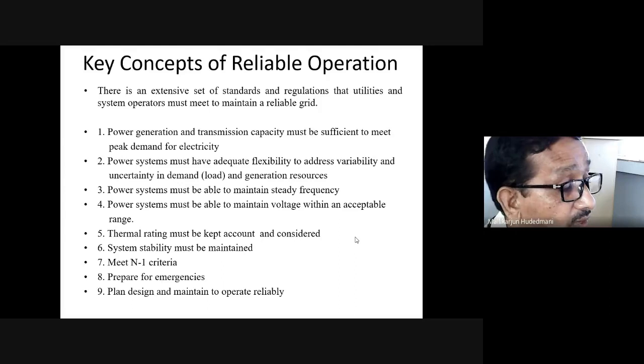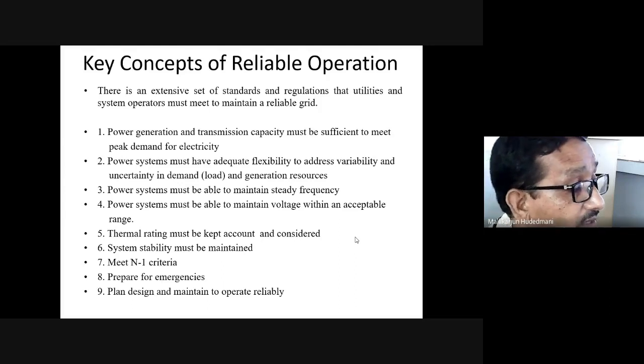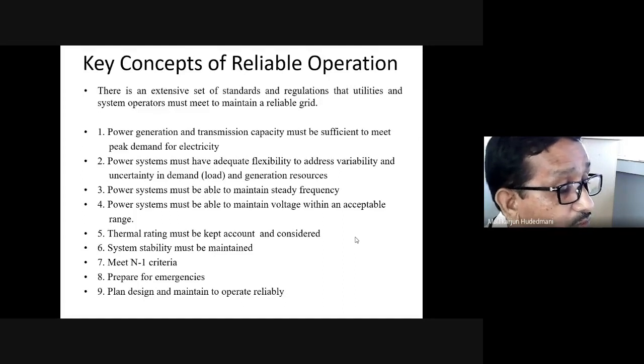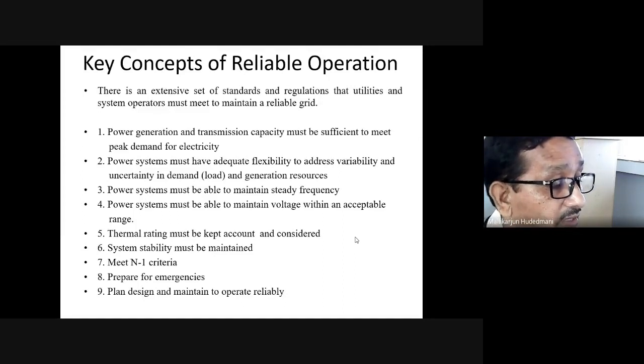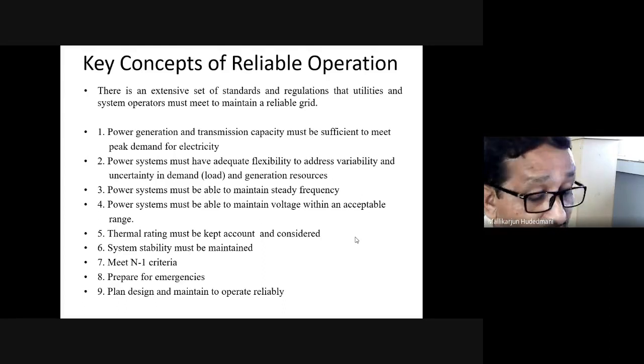If the variation is higher and inductive loads unnecessarily absorb higher power for doing nothing, that will cause a pulsation, additional loss, additional heat to just get into the other side, which is not required. Therefore, frequency must be maintained very suitably. So, the power system must be able to maintain voltage within an acceptable range.